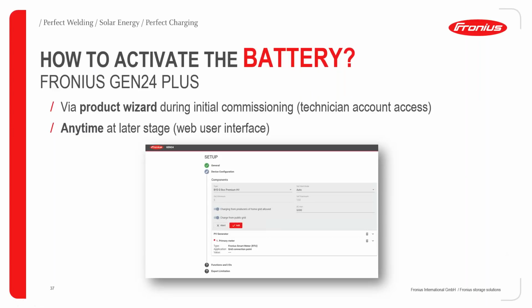If all the wiring is done and the battery is configured, you do the initial commissioning of the inverter. There's a step via the product wizard where you add this battery - device configuration, components - and if everything is correct with the communication, it should pop up automatically.